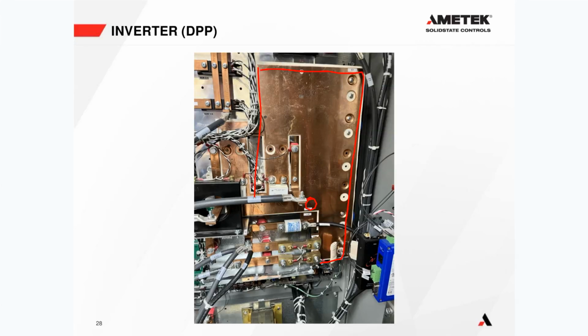So this outside copper that you can see is the positive DC going into the inverter bridge. And then here there's a hole and white behind it. That white is transformer paper, an insulating paper that separates two sheets of copper. So right behind this sheet is another identical sheet of copper separated by a transformer lamination, so they cannot touch each other - they don't short each other out. So that is the positive and negative going into the inverter bridge.